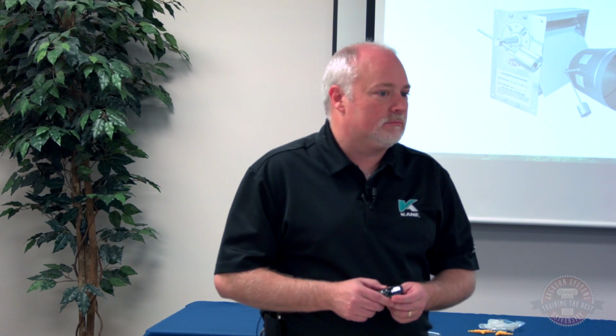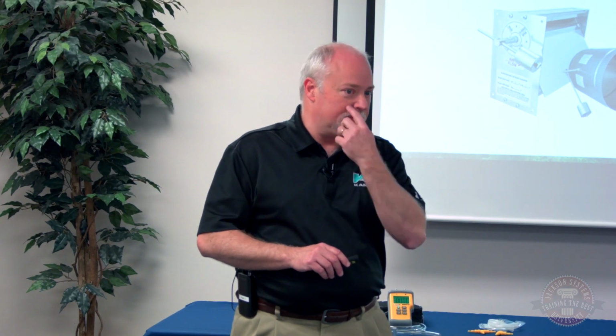Yep, got another question. Mike asks, how many scale settings does the EM201 have? Okay, we've got four different readings we can take. As far as what it will read to, it reads out to thousands, three digits. If he's thinking of a scale like on a multimeter, what scale do you set for voltage, it reads out to three points, so thousands. And if he's talking about scale as far as which readings, then we've got pascals, inches of water column, PSI, and so forth. Very good question.